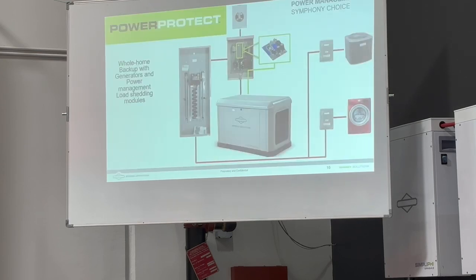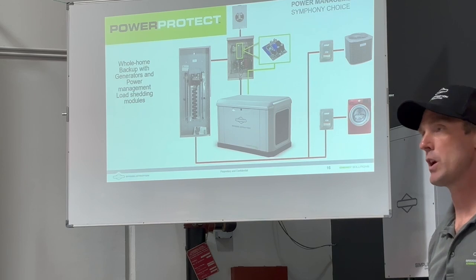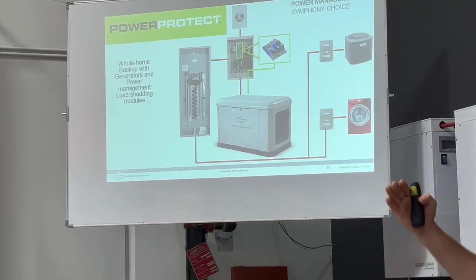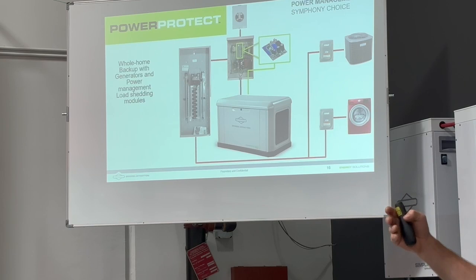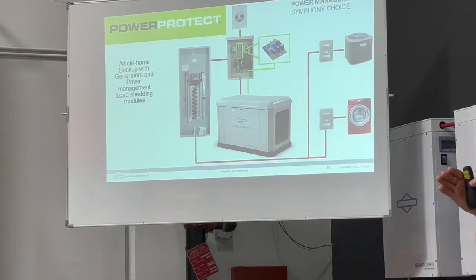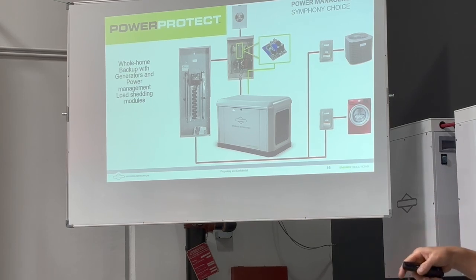So it manages those power inputs. I do point out here at the beginning that we have load management with our generators, but it's a very different type of load management. With a generator, you don't want to overload the generator. So our load management with our transfer switches and our generators sheds loads based on how much power is being drawn from the generator. If you've got a 20K generator and you get up to maybe 16K and you can see the generator's getting close to its limit, you might drop off a bigger load. It incrementally will add loads onto the generator so as not to overload it. That's what our load management looks like with the generators.